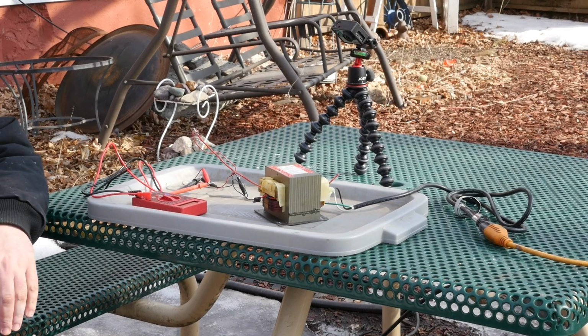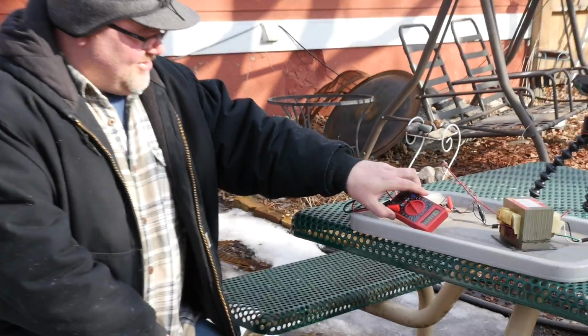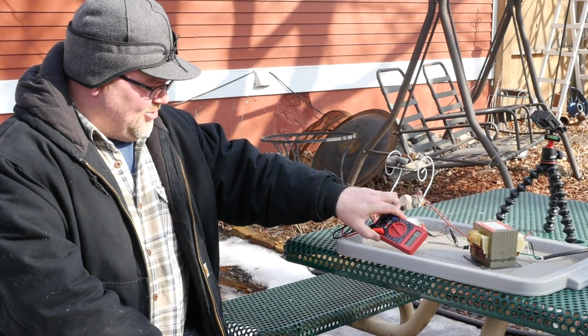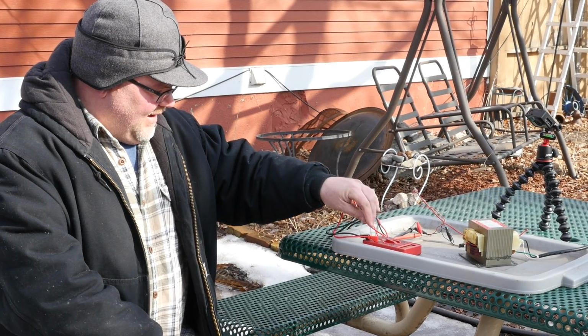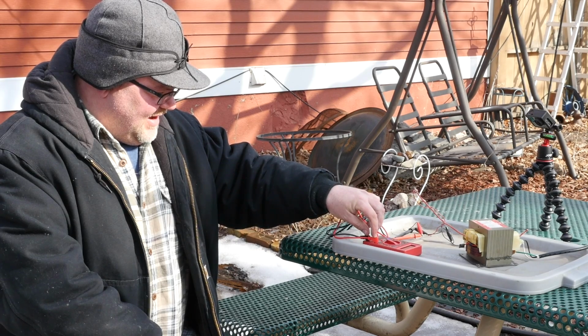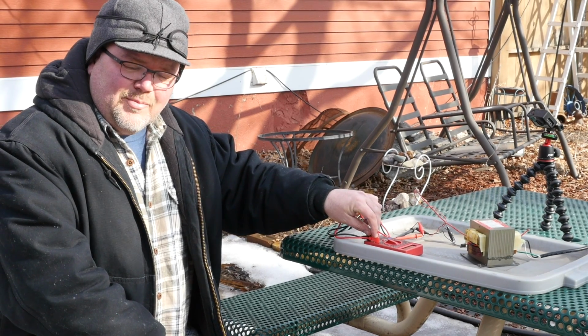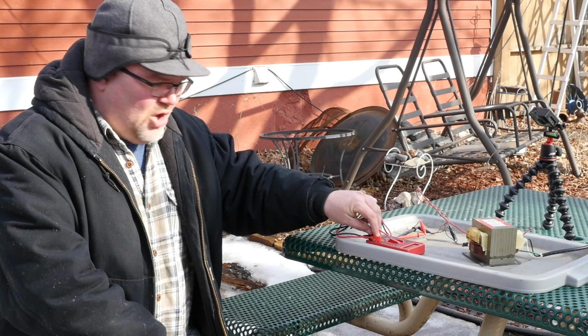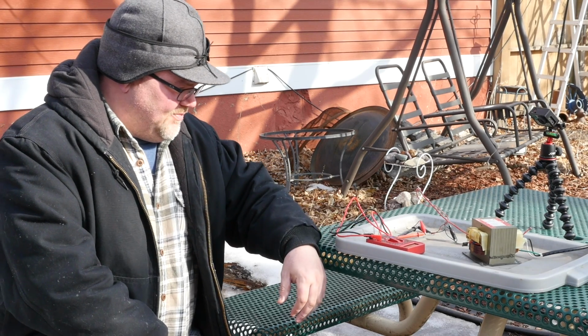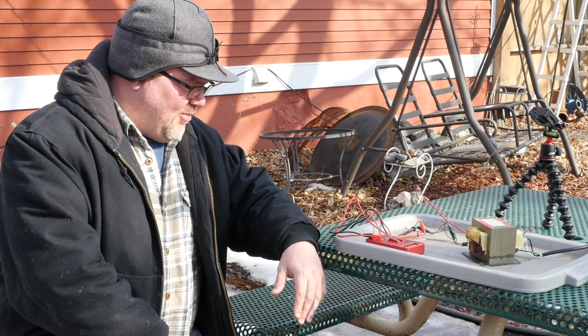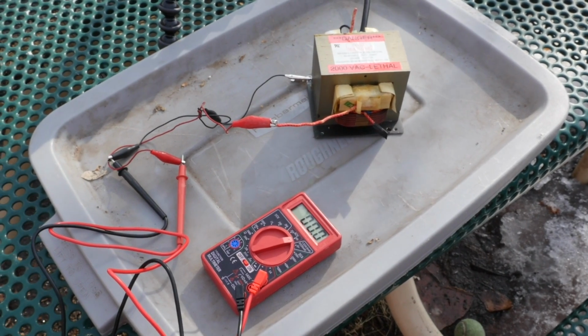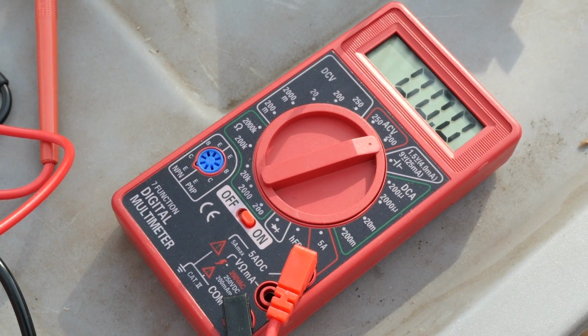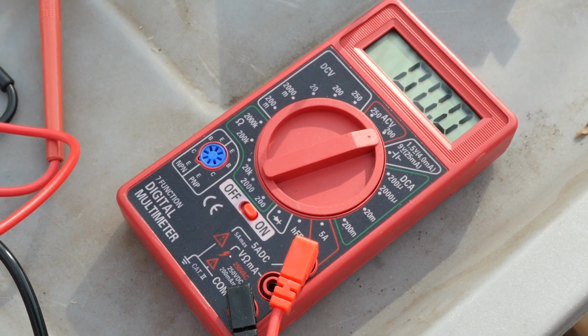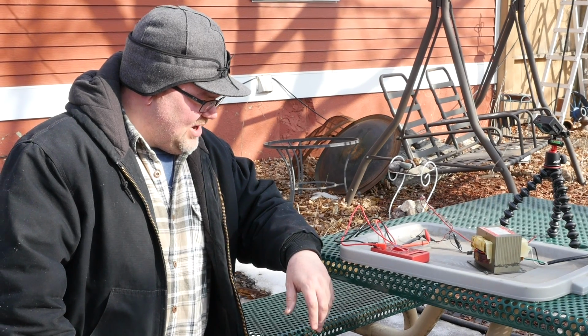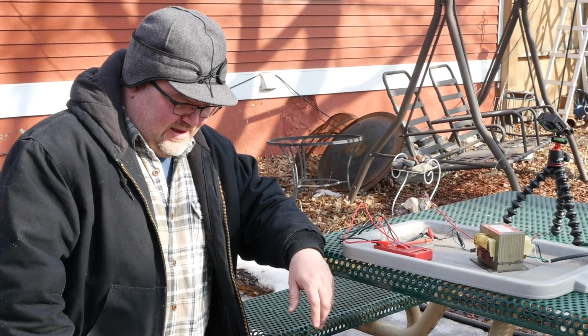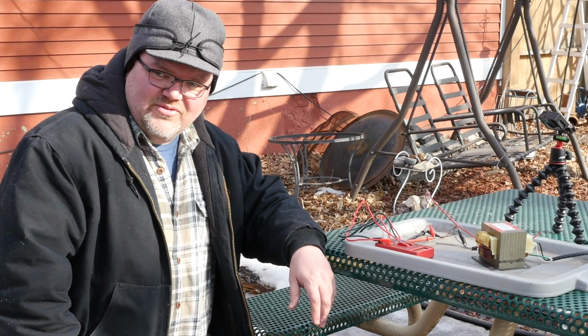Okay, so we have here the world's finest Harbor Freight $7 multimeter. I have put the test leads in the current position to present the low impedance load to the transformer. When I plug the transformer in, it'll be 2,000 volts, low impedance. It should act as a short circuit. If the input protection on this is sufficient enough, it should just blow a fuse.